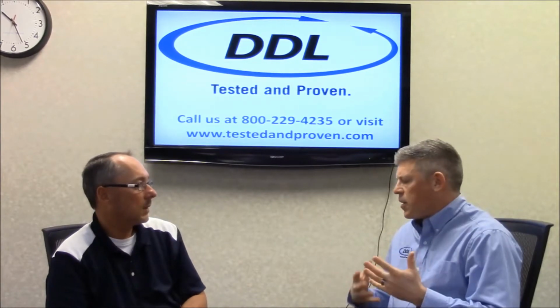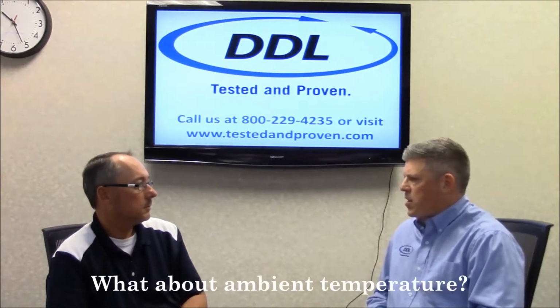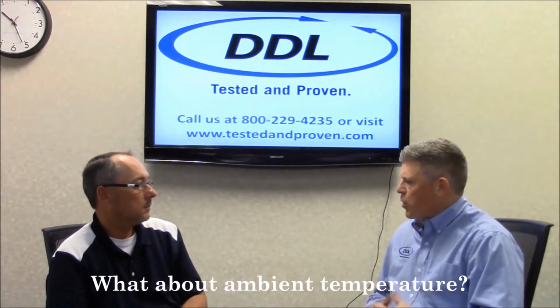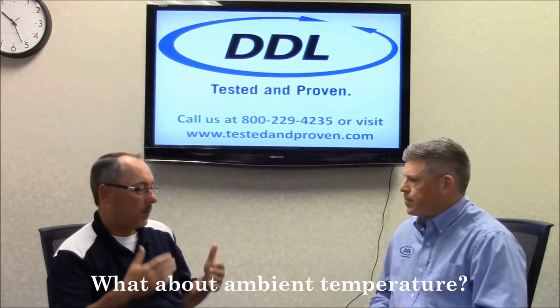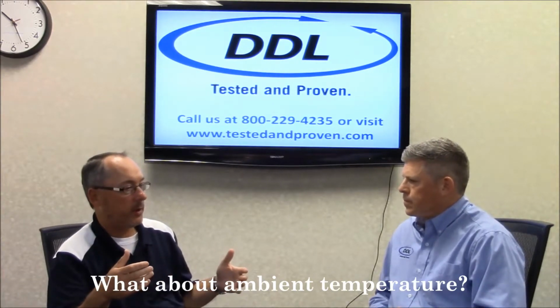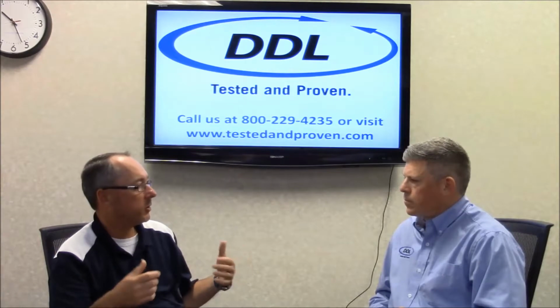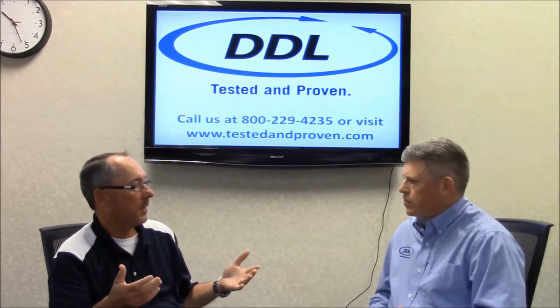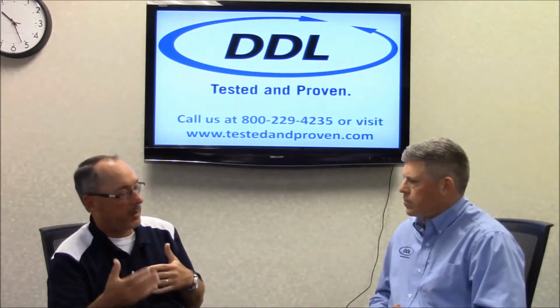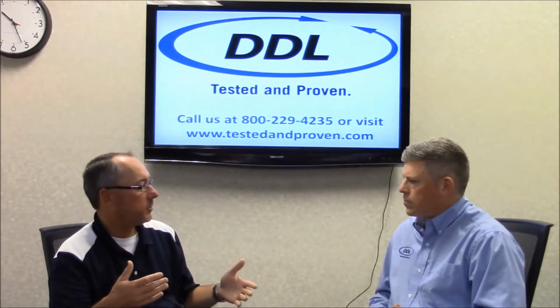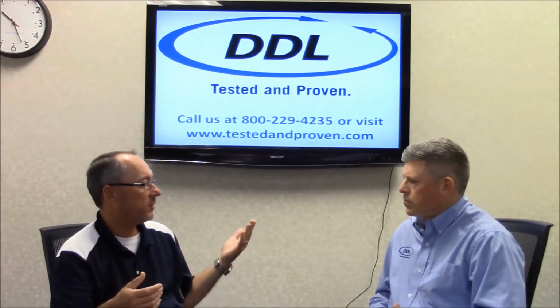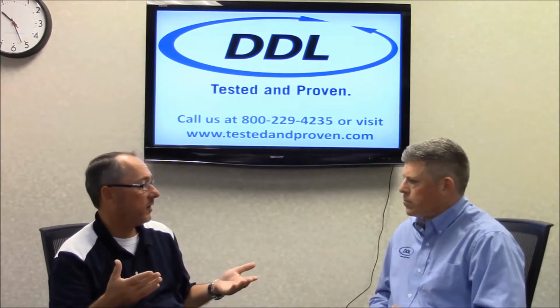So Scott, help me out with the ambient temperature and how that's used in the accelerated aging calculation. Sure. With the accelerated aging calculation, you have to pick your elevated temperature that you want to age your samples at. And then, per that calculation, they want to know what ambient temperature you'd like to use as well. So let's say I'm using a test temperature of 55°C.